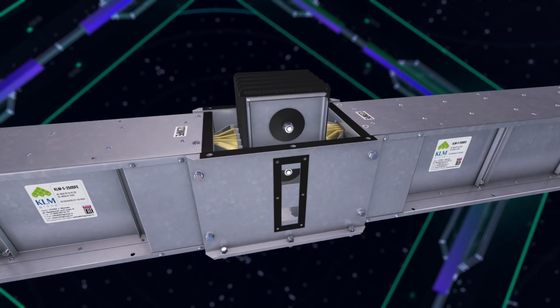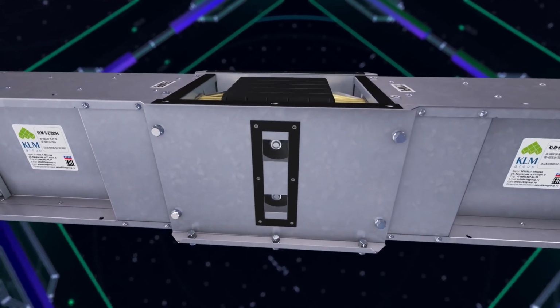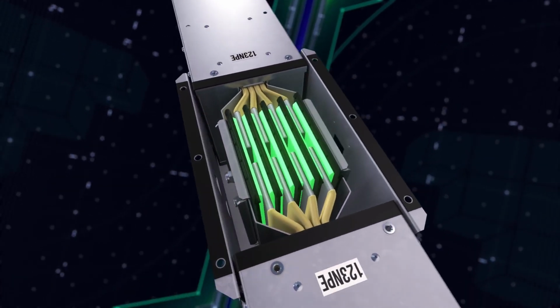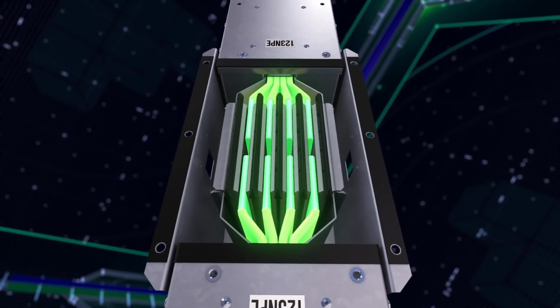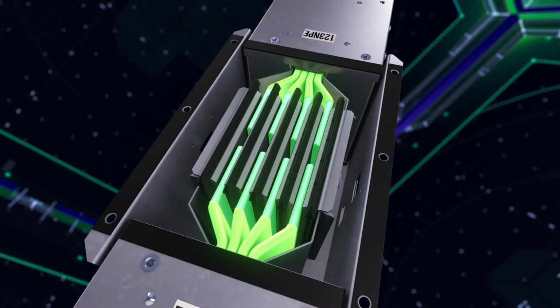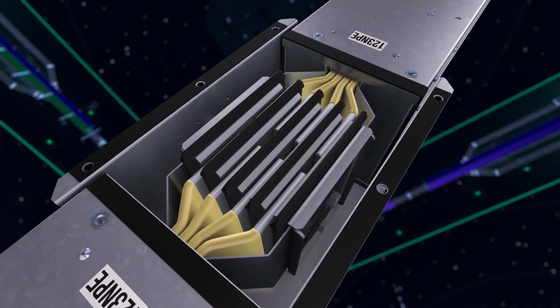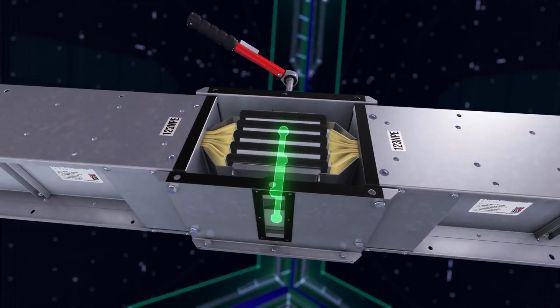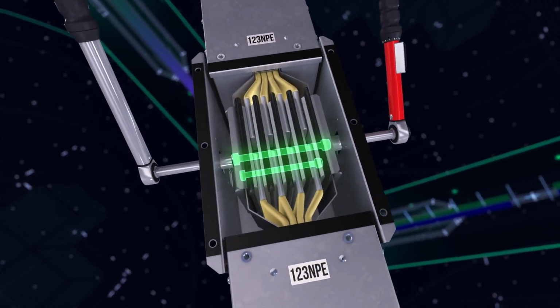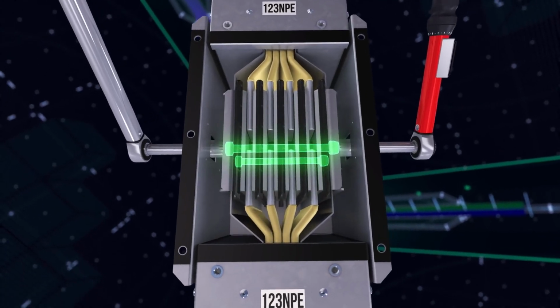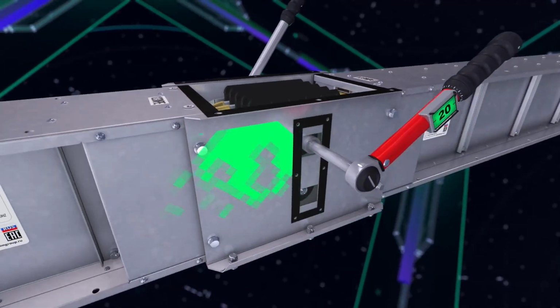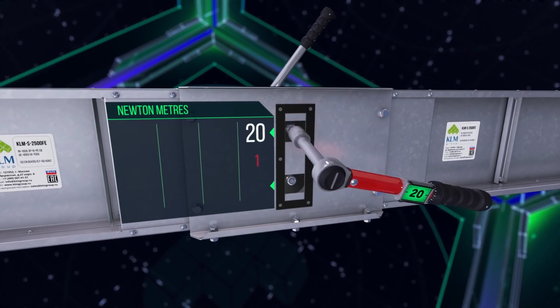Install the junction unit. Make sure that the contact plates fit tightly against the current conducting parts of the connecting sections. Standard assembling requires uniform and tight contact of the contact plates. Tighten the junction unit clamping bolts in rotating sequence while holding the bolts fast from the other side. This procedure should be performed with a torque spanner in 4 stages using the following torque settings.